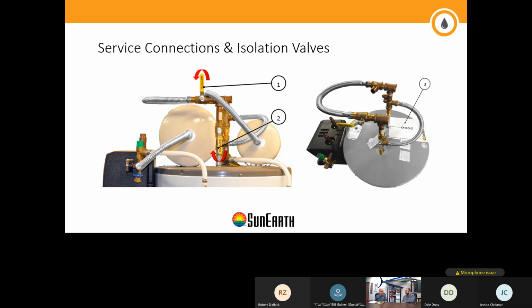Usually we have an isolation valve for an entire bank of collectors so we can basically shut off a bank. For example, if you have an array of 3 to 4 banks, we shut off one bank, the rest of the array is working, and we perform service on that specific bank of collectors. That's the whole purpose, that's the reason behind it. It's for service purposes, for replacing a broken collector or a leaking tank, something like that. If you have 50 collectors and every collector has to have isolation on it, that's excessive.